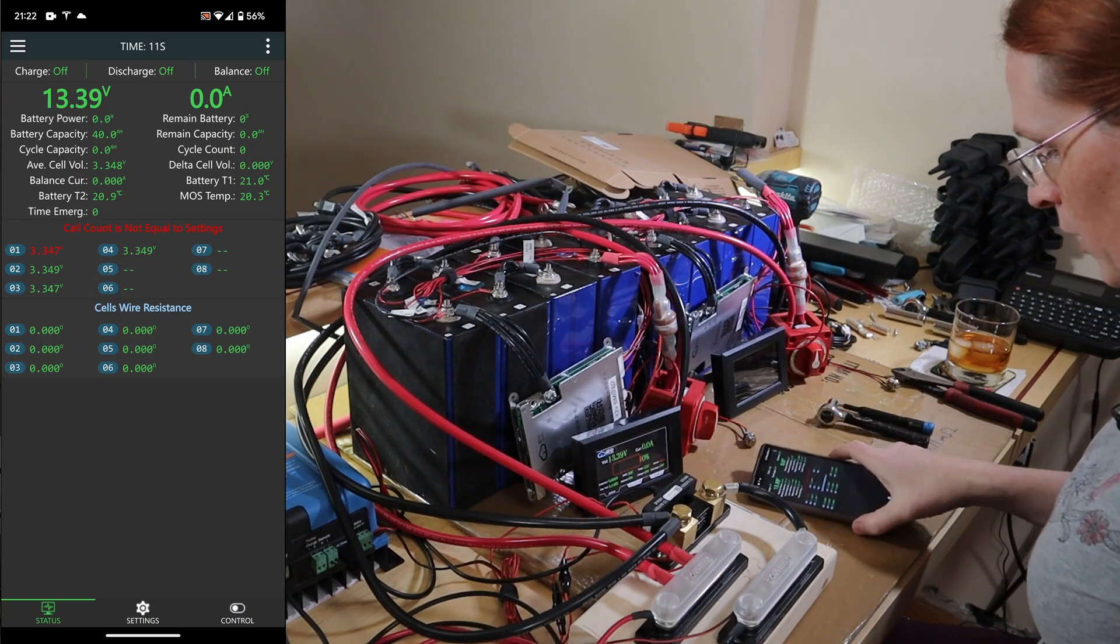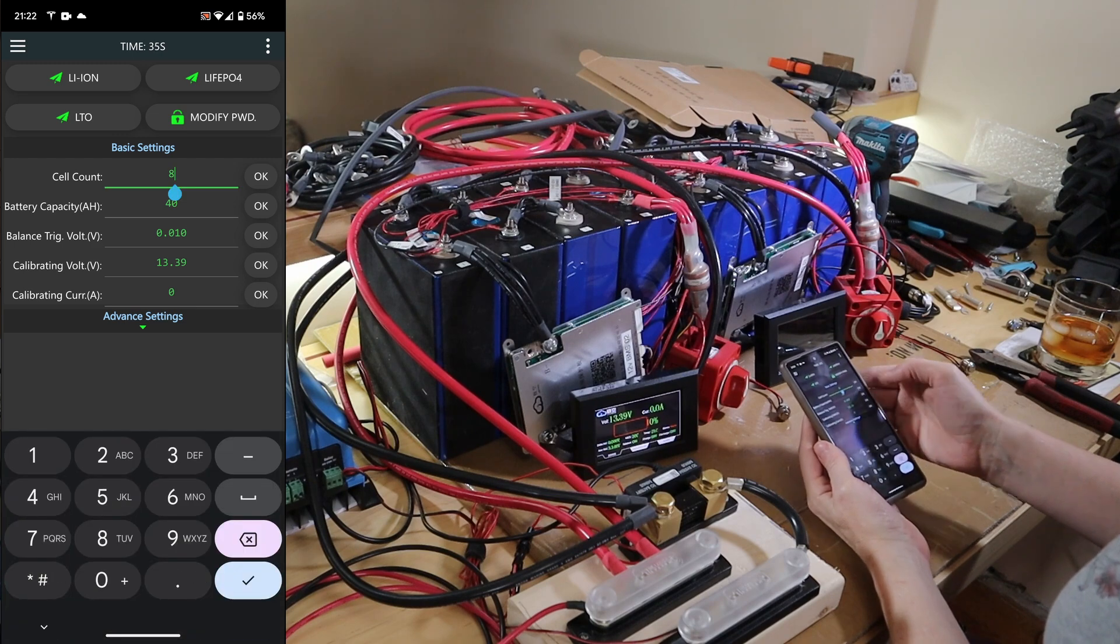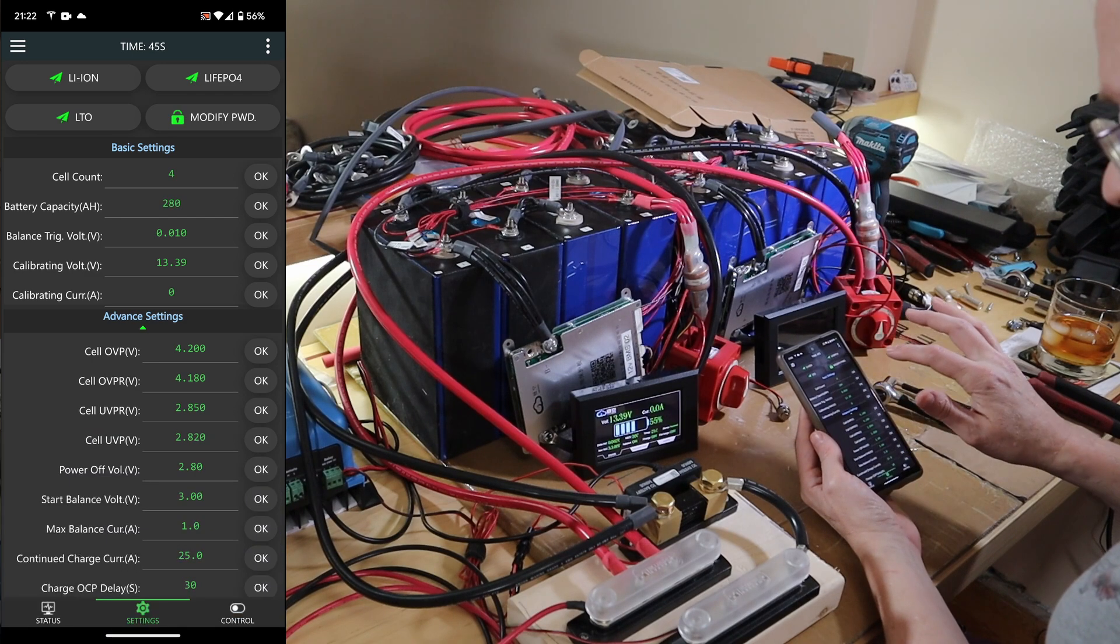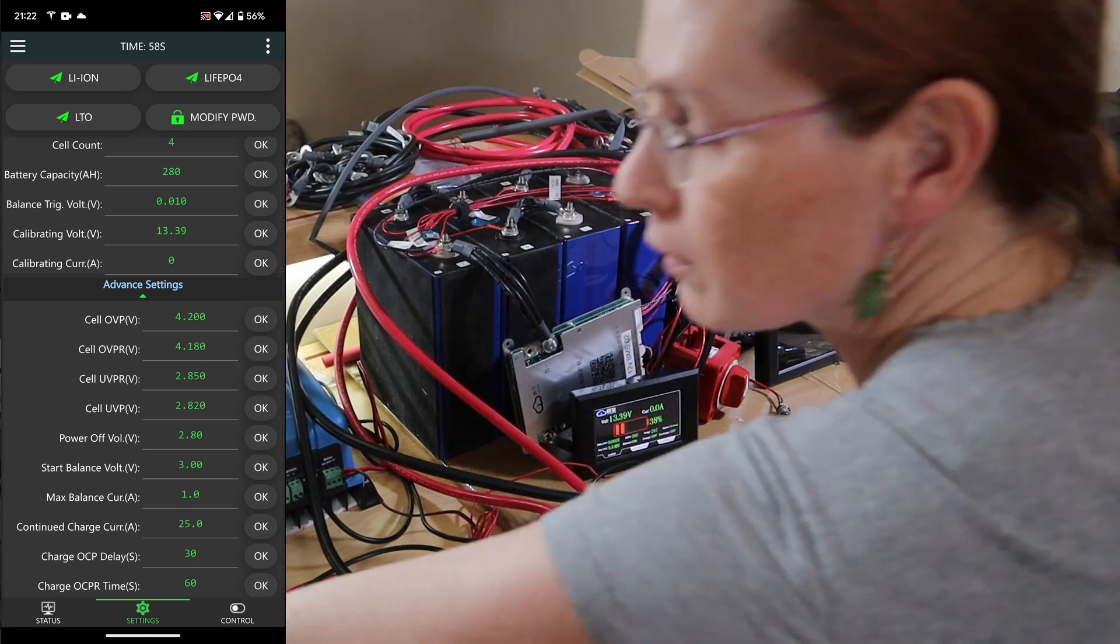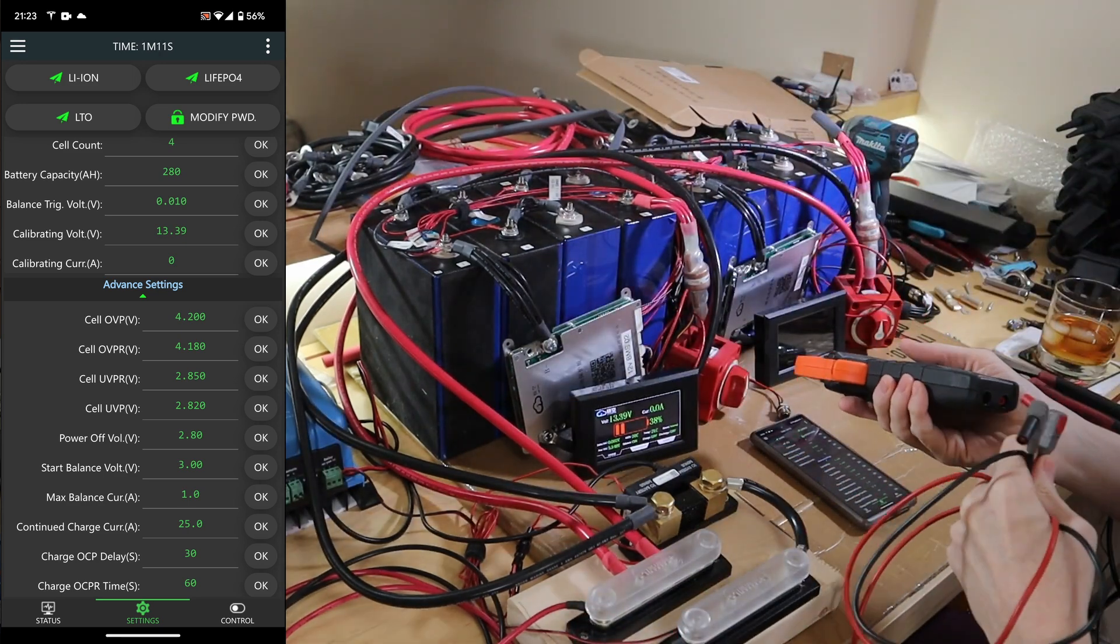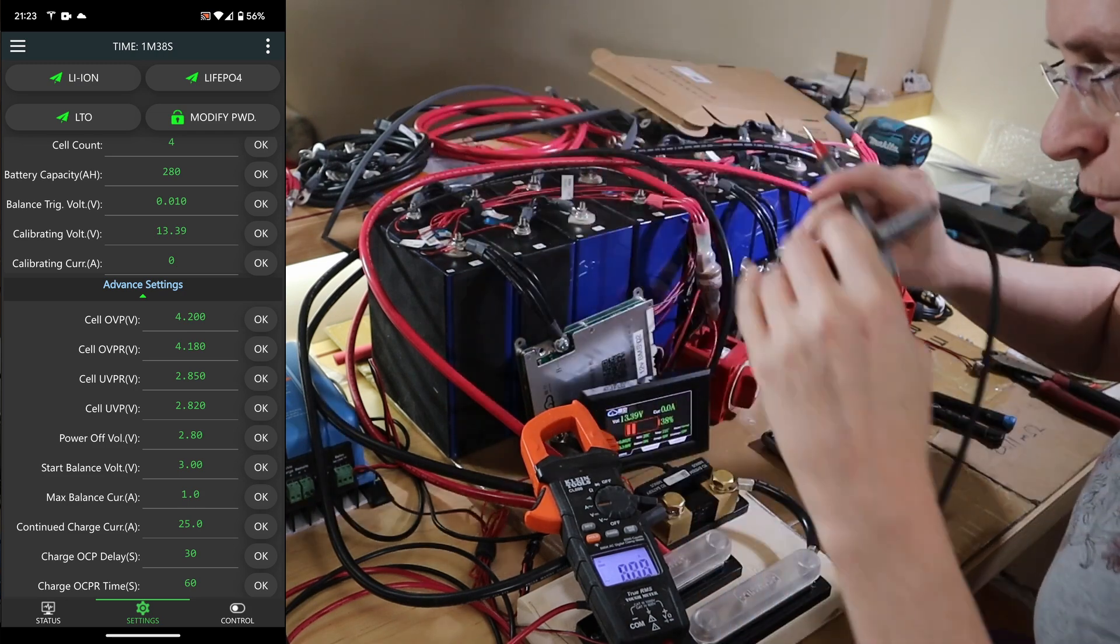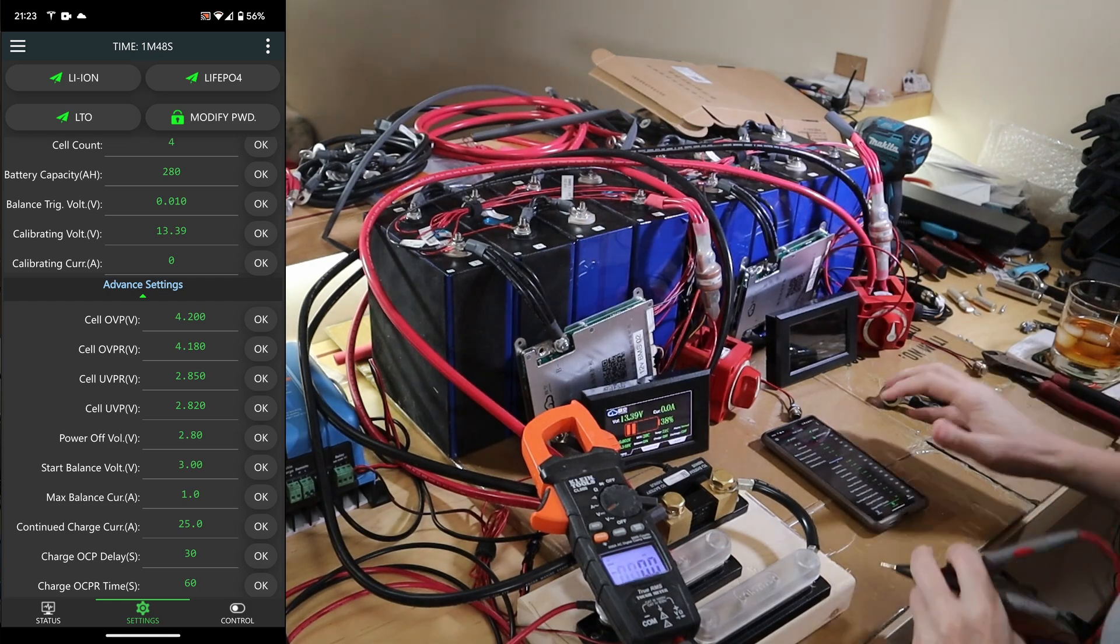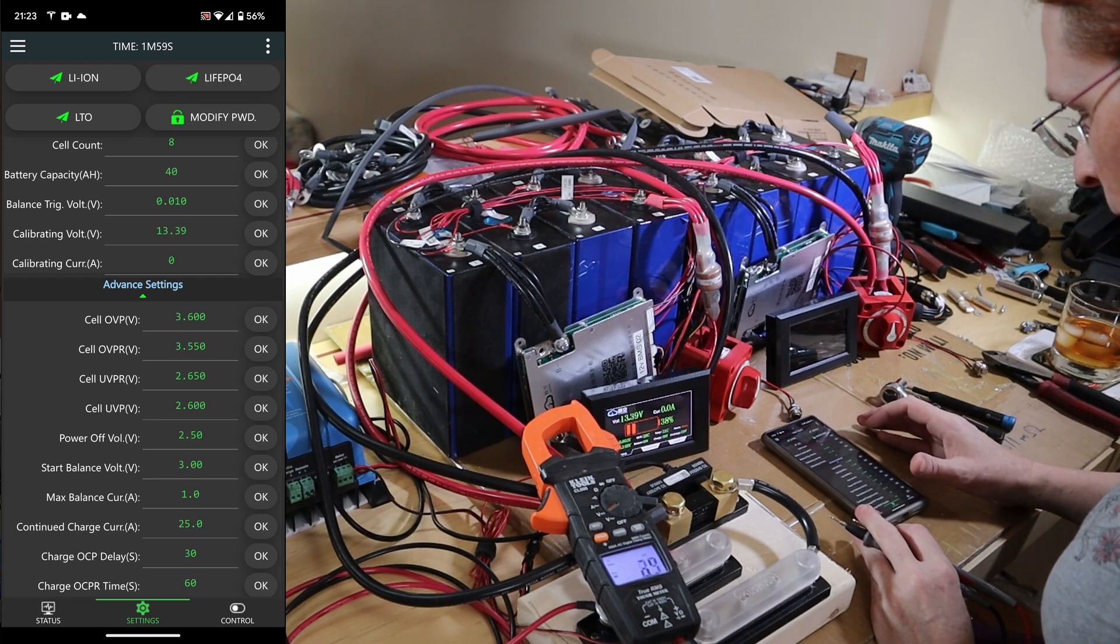It's booting. And there it is. Alarm. Cell count not equal. That's expected because it's thinking there's eight. So let's go into settings. Let's change this to four. We're going to set the battery capacity to 280. The state of charge dropped. Calibrated voltage. It says using the AC only clamp amp meter. This is my voltage standard bearer. I'll calibrate the voltage. It is 13.31 and it's reading 13.39, so we're going to change that to 13.31. We got to change this to LiFePO4. There we go.